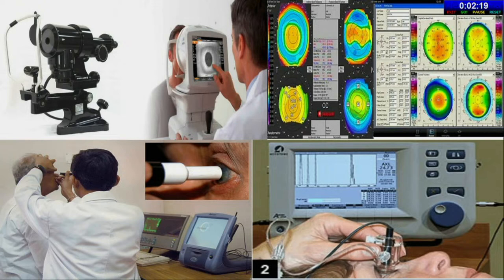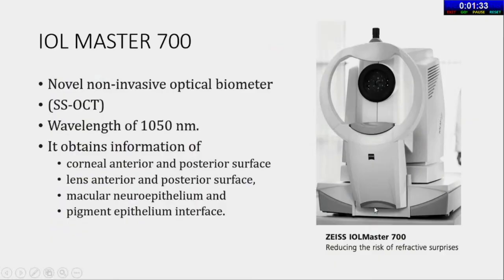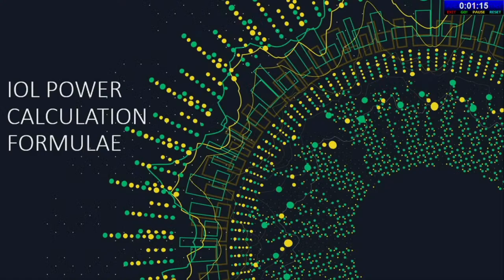Can you identify all the instruments shown? They include an automated keratometer, a pentacam, a contact A-scan, and an immersion A-scan. The newest instrument is the IOLMaster 700 - a novel non-invasive optical biometer with a wavelength of 1050 nanometers. It can capture information on the corneal anterior and posterior surfaces, lens anterior and posterior surfaces, macular neuroepithelium, and the retinal pigment epithelium interface.